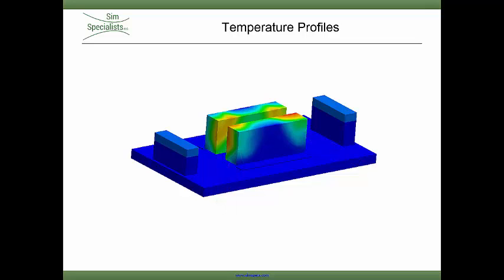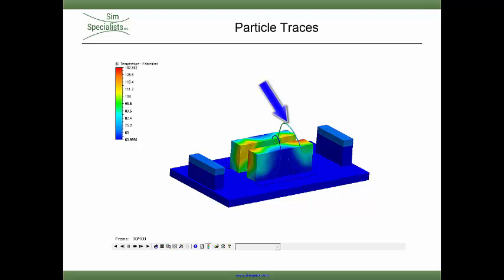To further investigate this temperature rise near the end of the rows, we can add particle traces. The particle trace on the right recirculates back into the server after passing through and rising in temperature during each pass.